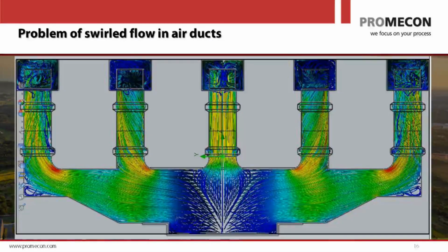Another problem that I mentioned is we measure a vector. Why is a vector important in measuring airflows in power stations? Have a look at this one. This is a manifold of a combustion engineering boiler in South Africa. You can see on this one that the bulk air duct, which is the blue rectangular area on the bottom of the picture, this bulk duct comes more or less towards you. So the airflow comes more or less out of your screen that you see. And then for the middle manifold, the airflow bends upwards. So it turns by 90 degrees. And therefore you can see it goes up, but there is no swirl. It goes in a straight line.